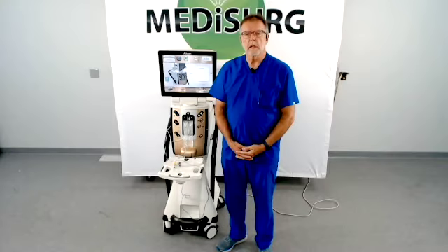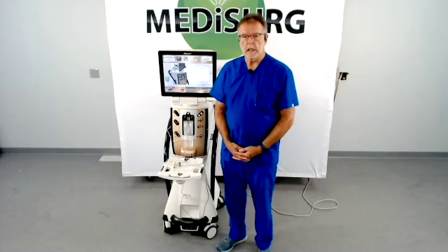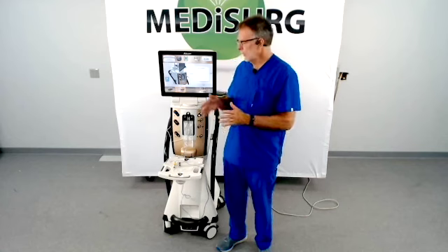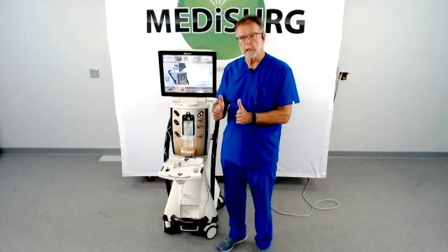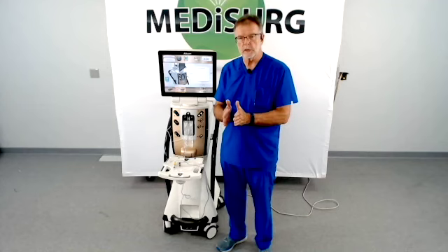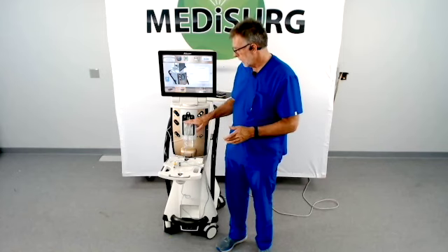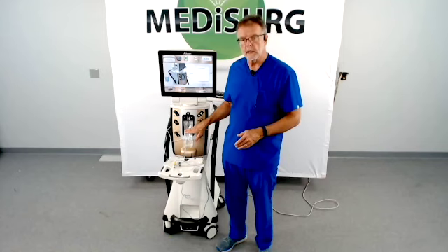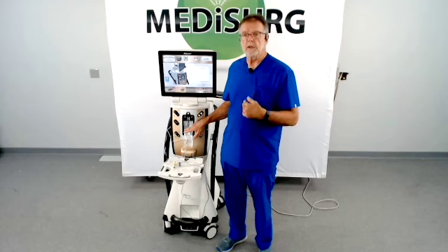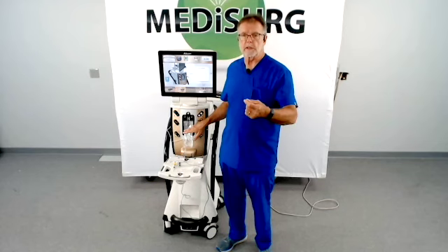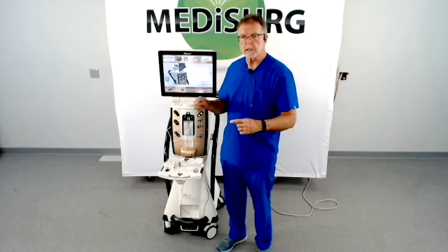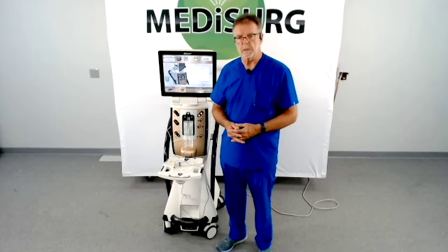Our next test is the bag sensor test. So the IV bag, when it fits down into its holder, there are pressure plates that squeeze against that bag, and it looks at and measures the pressure on a transducer to see if the pressure is correct. And then it's backed up by the transducer inside the cassette. And now with the new Sentry system, there's a transducer in the handpiece. So there's 3 places that it measures the irrigation pressure.